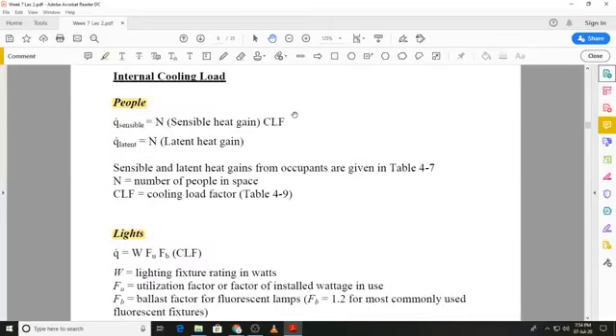We now come to the internal cooling loads. One is the load due to occupancy or people inside the conditioned space. I told you earlier that occupancy causes both sensible and latent heat gain, and what we will find out is that the sensible heat gain per person, depending on the activity that person is engaged in, will be given to us, or we will read it from a table, multiplied by the total number of people. And if it's a sensible heat gain, we also have to multiply it by the cooling load factor, because people also emit thermal radiation, and that has to be accounted for by using a CLF. The latent heat gain per person is directly multiplied by the number of persons in the conditioned space, and the total load due to occupancy will be the sum of the sensible and latent heat gains.